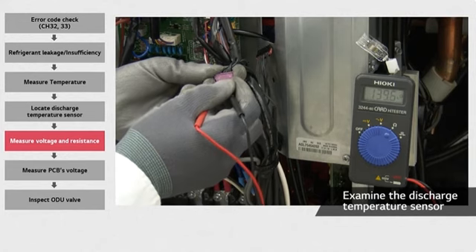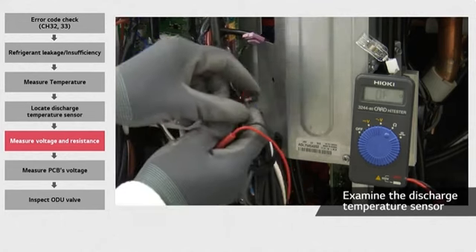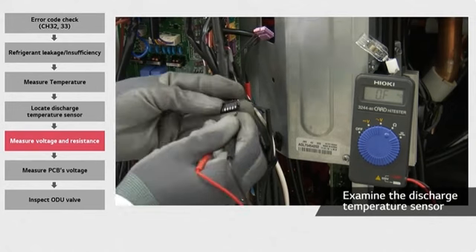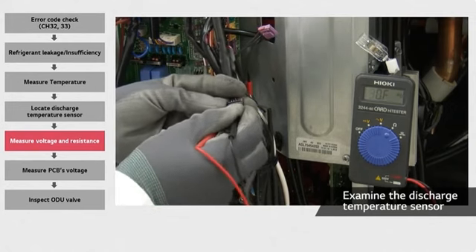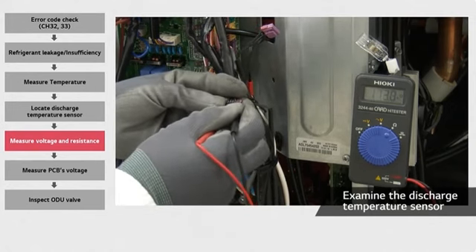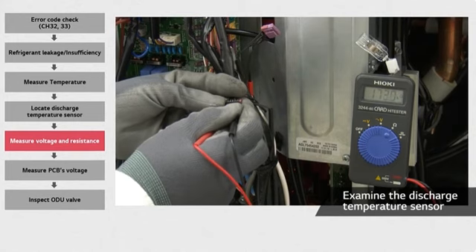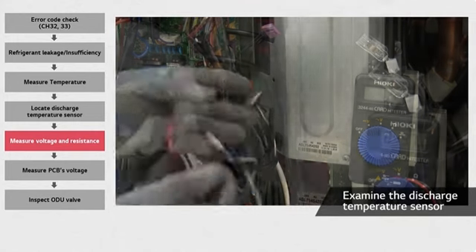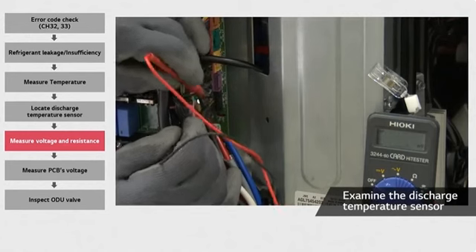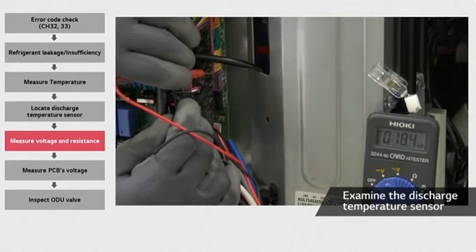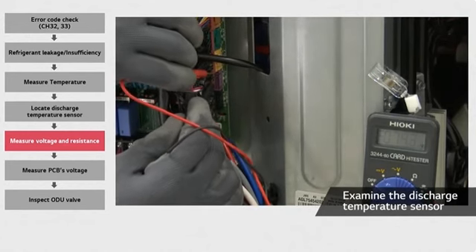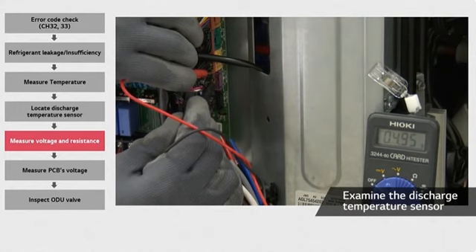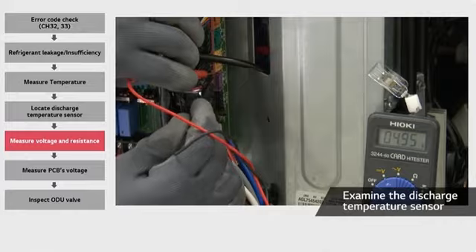If the resistance value is in range and it matches the discharge temperature, the discharge temperature sensor is normal. See the guidebook appendix for more details about resistance values. Inspect the voltage of the discharge temperature sensor. Check the discharge temperature sensor connector DC voltage on the external PCB. The normal reading is 5 volts.